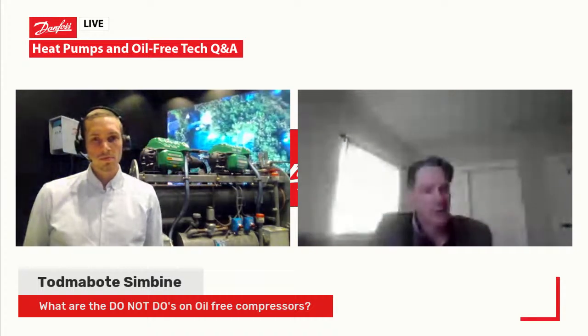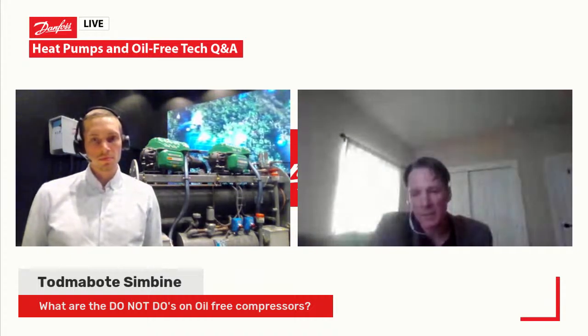Today, that limit is about 67°C. Going any higher is the critical 'do not' I'll highlight: as you go into the top of that centrifugal operating dome, your ability to turn up and turn down capacity becomes somewhat limited, and as we push further into that temperature range, those capabilities remain limited.